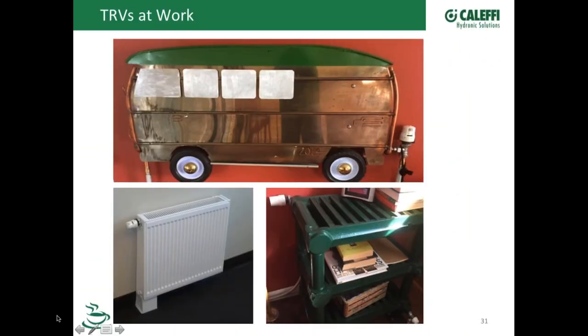And here's a couple of my jobs I'll show off that I've used some of our thermostatic radiator valves on. So I've just got a single little Alpha pump on my buffer tank, just sending water out all the time. And the only time that pump wakes up is when one of these valves in the bedroom here calls for heat. So there's your typical panel radiator. This is a little cast iron pantry radiator. I've got one up there. And this is a little radiator that I made for a Christmas present a couple of years ago. And it also has a thermostatic head.